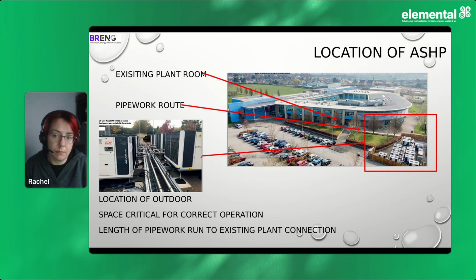But the third thing people always miss is the original selection has to be right as well. Because if the original selection is done based on a contractor choosing it to suit the cost for the school, they may choose smaller equipment that has to work harder for longer, which reduces its life expectancy. If you factor in that most of the time it's going to be running at 80%, sometimes 100%, but we can control it so it's not running at 100% all the time, you will prolong the life of the unit. So the 15 years that CIBSE recommend, I think that's general guidance - if you're over 15 years, you're doing well. If you're under 15 years, well, that's kind of because it's not being looked after.